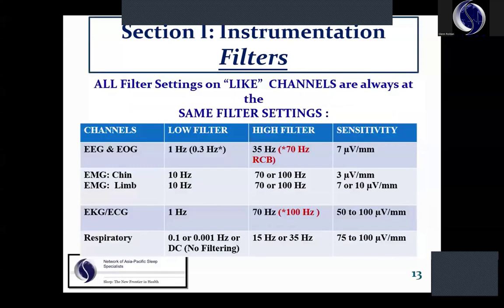All filter settings in like channels are always at the same filter settings. Now, one thing I want to talk about here, from the AASM guidelines for EEG and EOG, they're recommending a high filter of 35 Hertz. We'll talk in a little bit, and we're also going to talk this afternoon about how important it is to use a 70 Hertz high filter, especially if there's a differential between seizure and sleep disorder.